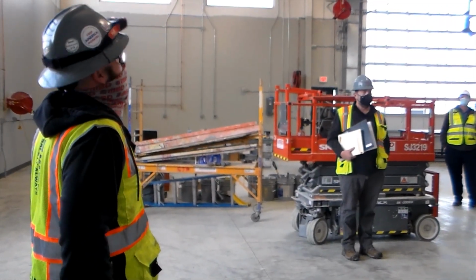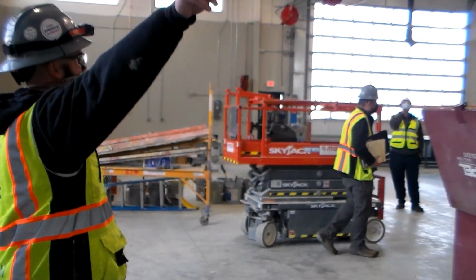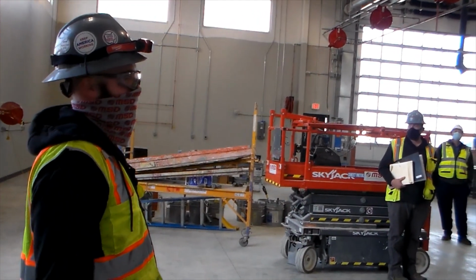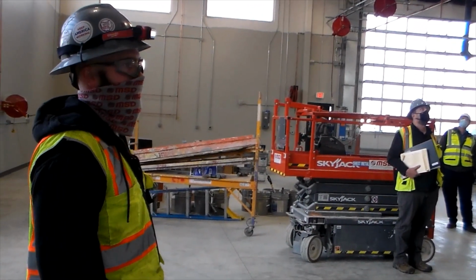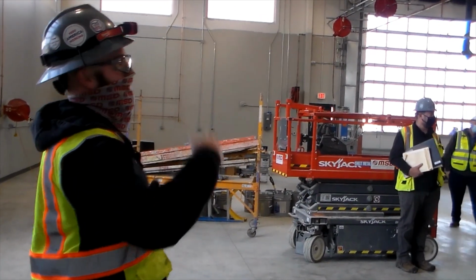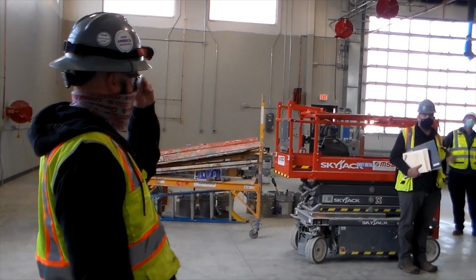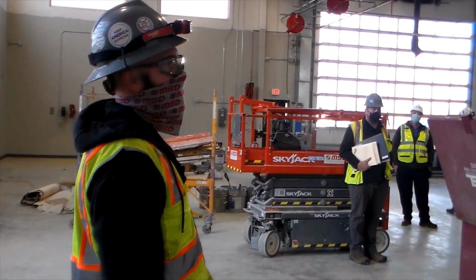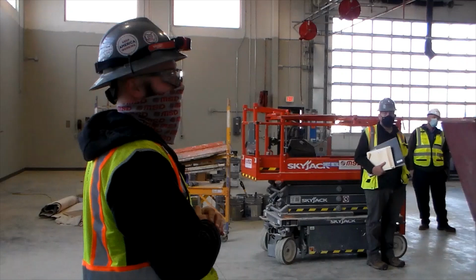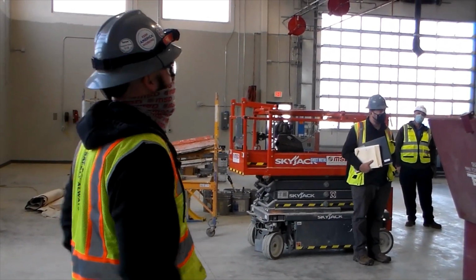And these are natural gas. The regulator is right above the mezzanine stairwell that feeds all 4 heaters in this area. There's pressure taps on each side of that regulator if you ever have an issue with the regulator. Each unit has a valve. Pretty much have your flame rod, spark igniter. Not really much maintenance to these. Just keep the dust buildup down. Pretty maintenance simple.